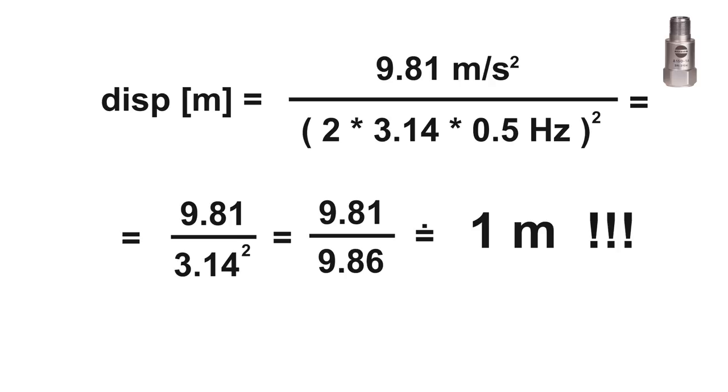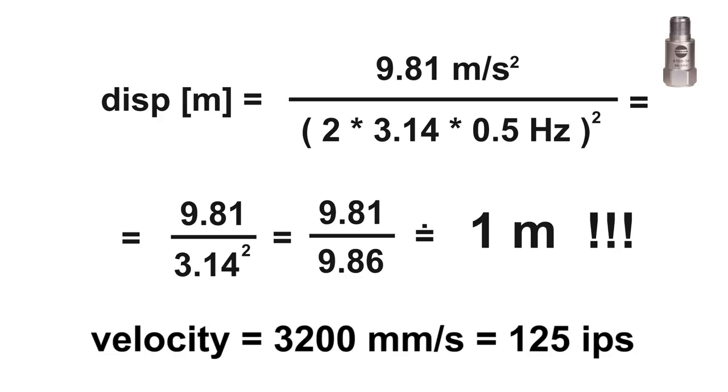The corresponding displacement level is 1 m. Not 1 mm. Really 1 m. No machine could work with such vibration level. The corresponding velocity level is 3200 mm per second. It is 125 inches per second. Impossible.